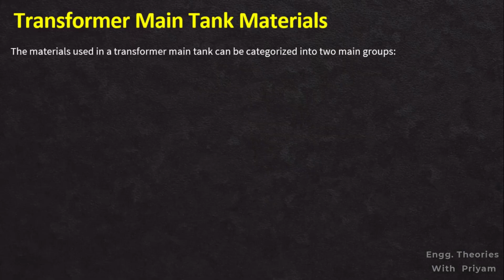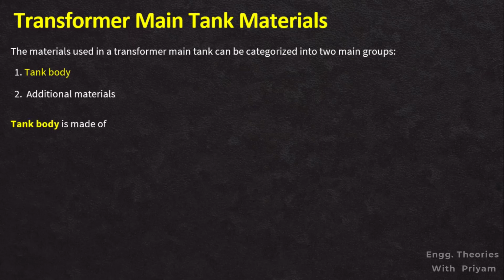The materials used in the transformer's main tank can be categorized into two main groups: the tank body material and additional components. For the tank body, steel is the most widely used material, along with less commonly used aluminum and stainless steel for specific cases. Steel is the most commonly used material in the transformer tank due to its affordability, strength, and weldability. Low carbon steel is preferred for its good mechanical properties and ease of welding.